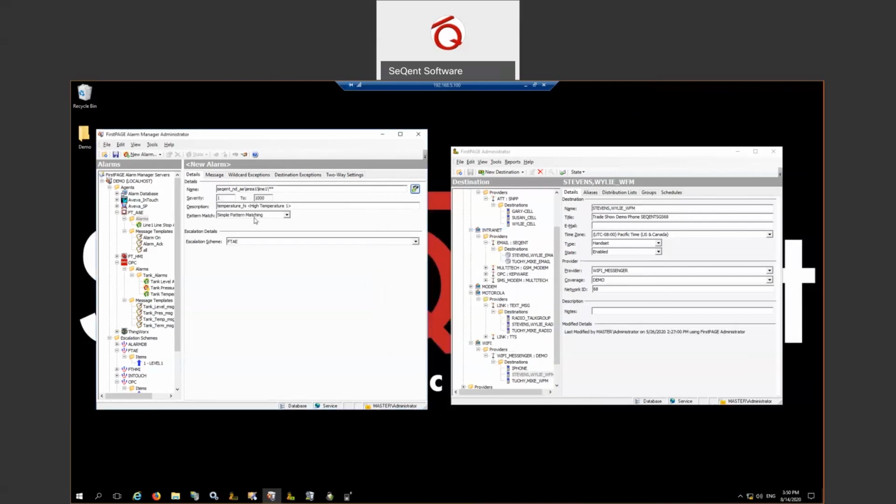We immediately switched to simple pattern matching, but we also introduced these wildcards and opened up the severity. So what this does for a user is it creates a one-to-many relationship where we can actually monitor multiple alarms without having to specify them within our software, which allows you to reduce configuration even further. So this can actually match potentially tens, hundreds, even thousands of alarms that you ultimately have in your system with only having to create one or potentially a few records.